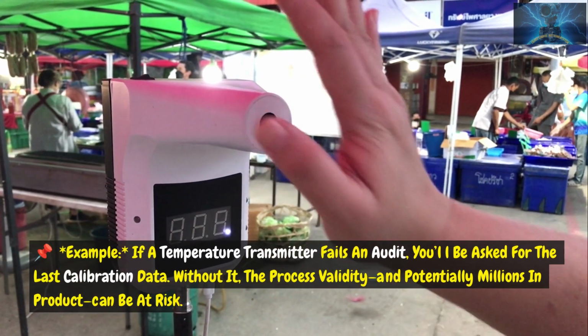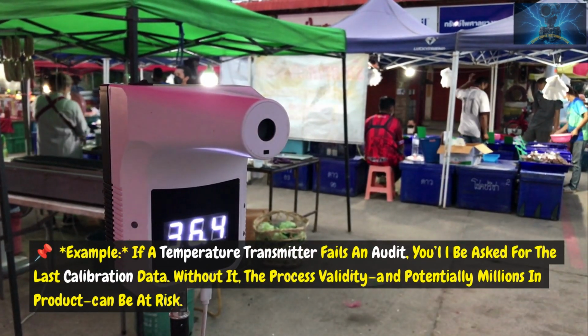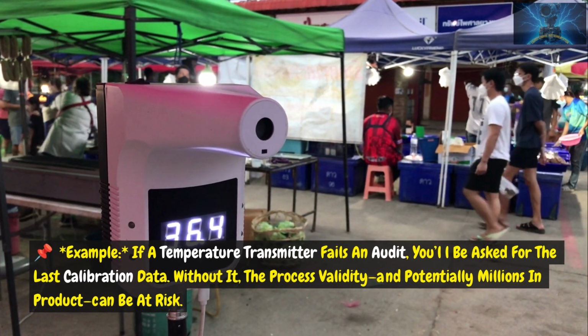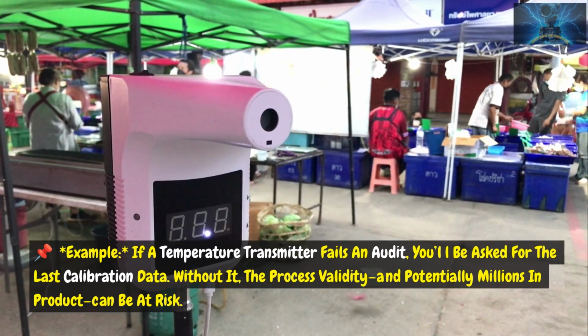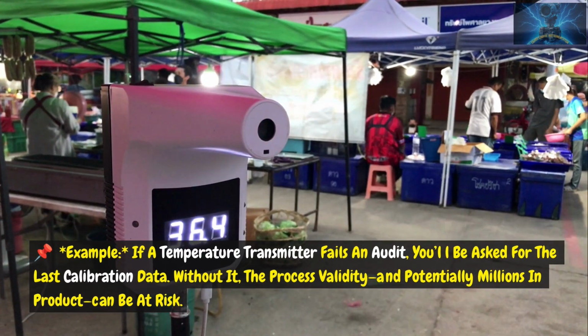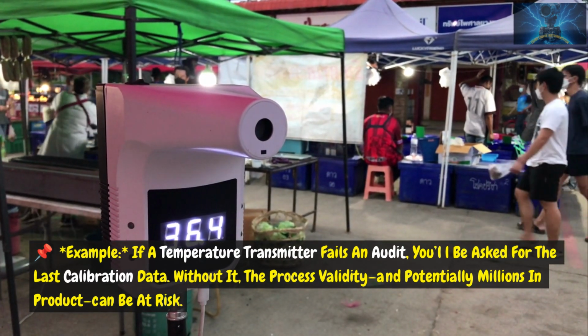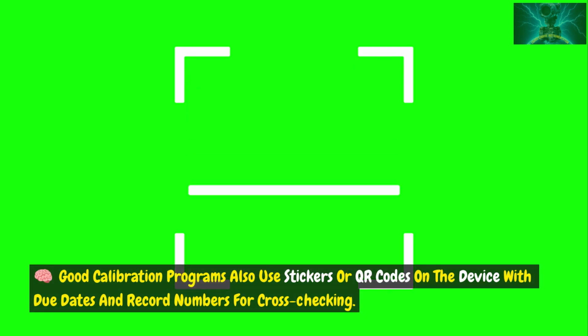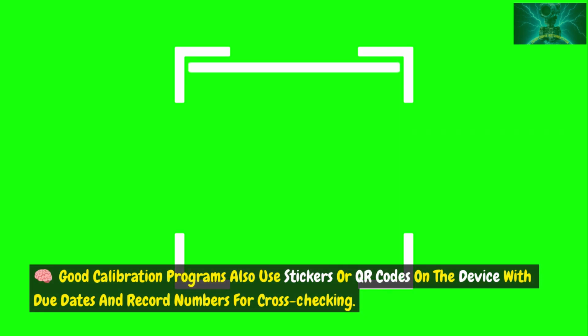Example: if a temperature transmitter fails an audit, you'll be asked for the last calibration data. Without it, the process validity, and potentially millions in product, can be at risk. Good calibration programs also use stickers or QR codes on the device with due dates and record numbers for cross-checking.